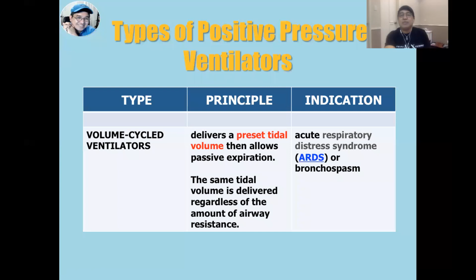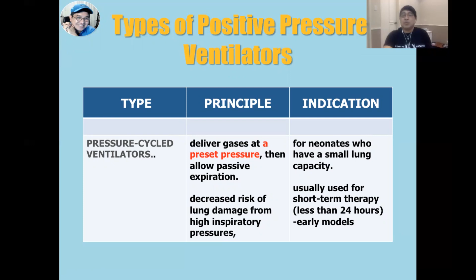So we also have pressure cycled ventilators that deliver a preset pressure. That's why it's called pressure cycled ventilators. Now, the advantage is that you have a decreased risk of lung damage from high inspiratory pressure. This is indicated for neonates. And for short-term therapy, those that require ventilators for less than 24 hours.